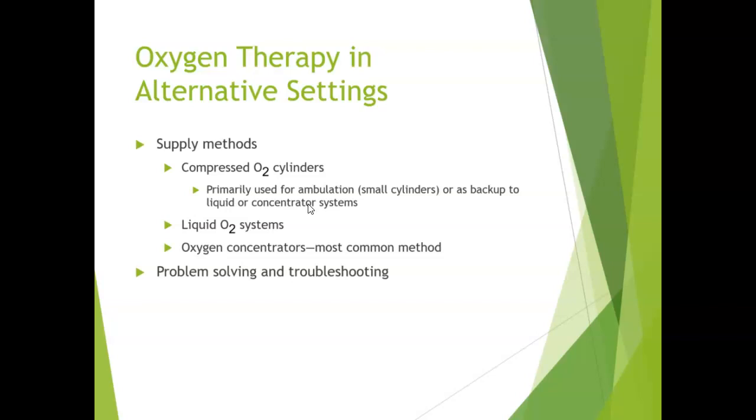Okay, so liquid oxygen systems. These usually are higher cost than the other delivery systems, so there's not a lot of places that will use them. But the advantage of them is that they can store large amounts of gas in small spaces. But like I said, they're more cost prohibitive than other methods.